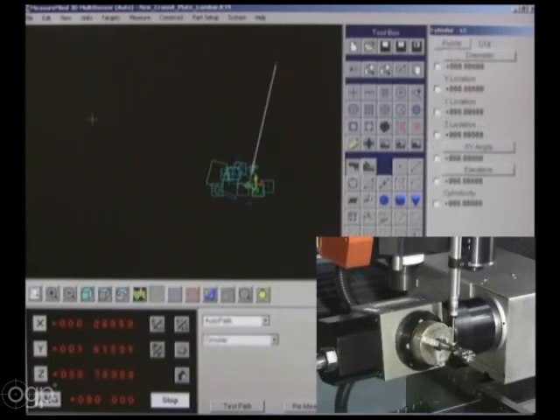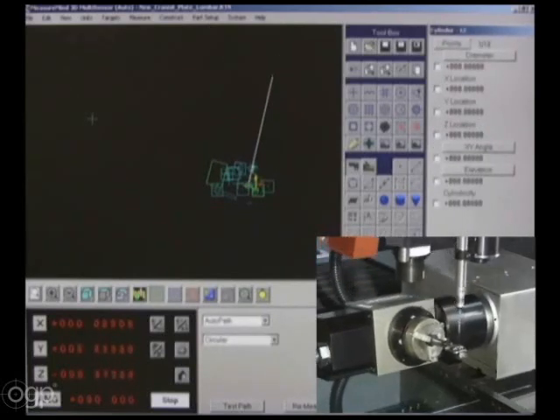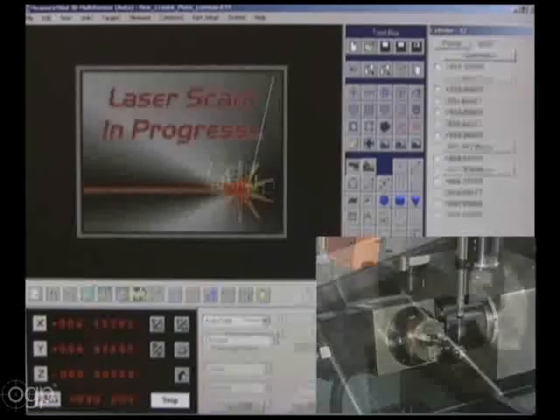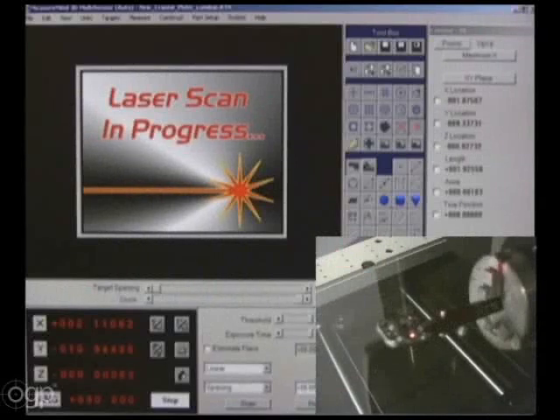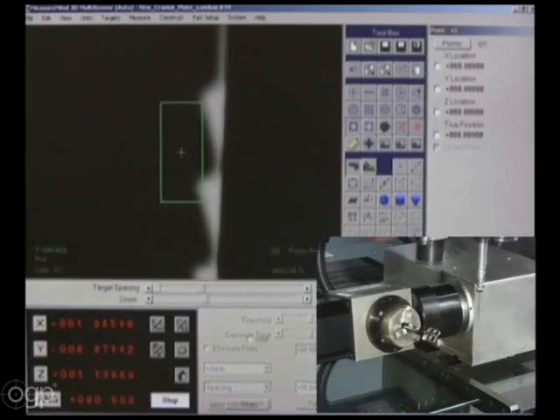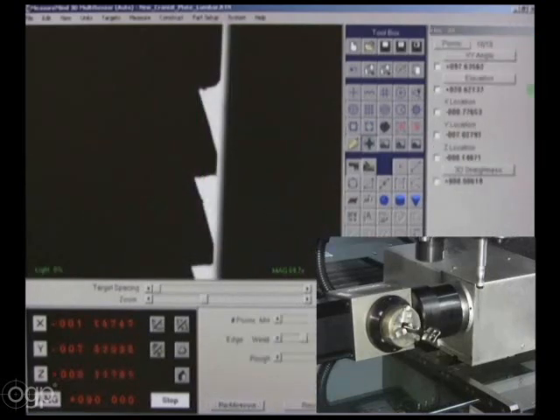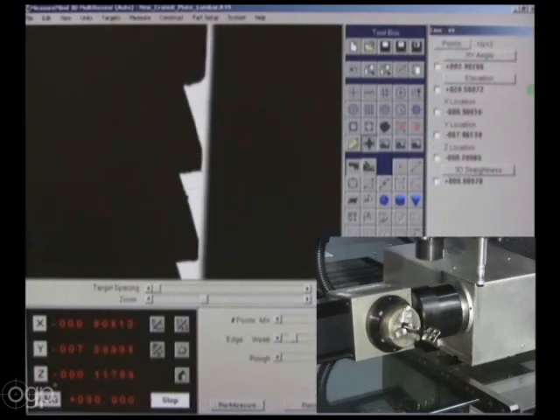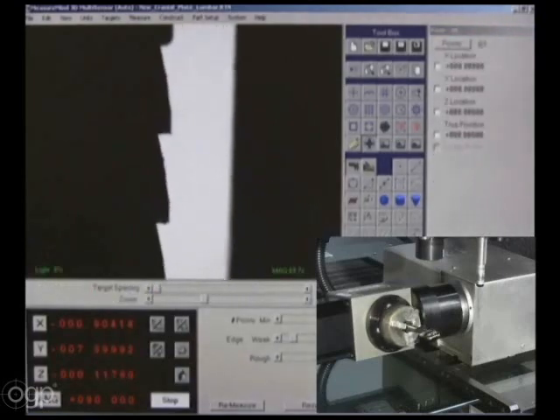So here, just as a start, notice the probe orientation in the model window. And then as this does its different measurements, it's using video and touch probe to set up the datum structure here. And then it does a rotation. It actually did a rotation in both axes, a relatively large rotation on the primary axis and a small rotation on the secondary. And then it used the touch probe to set up some datums. Now it's doing some laser scans, and those laser scans are relative to the datum that was set up. And so now it's rotating around to the opposite side of the part.